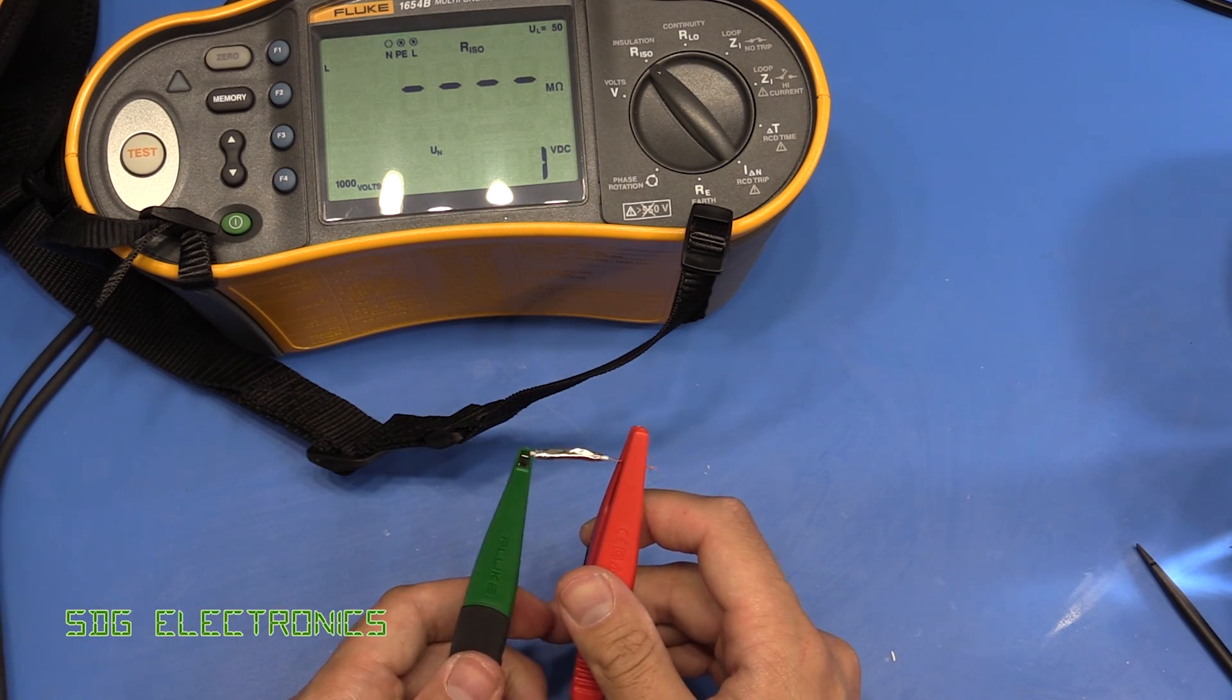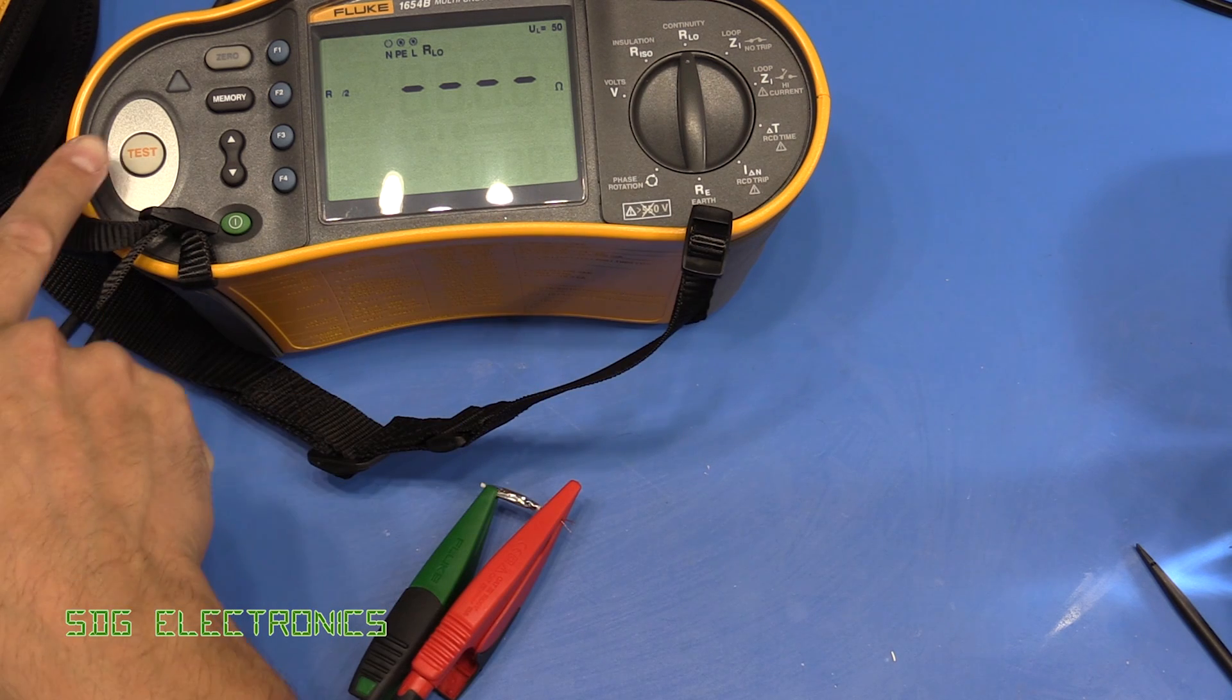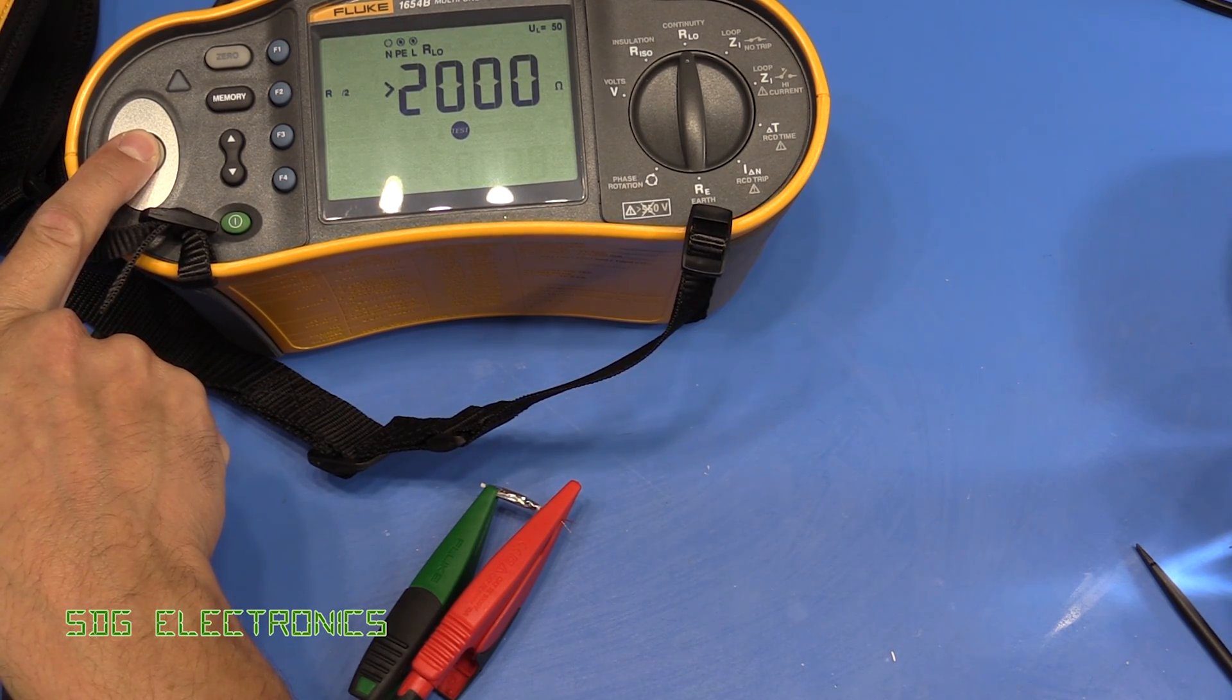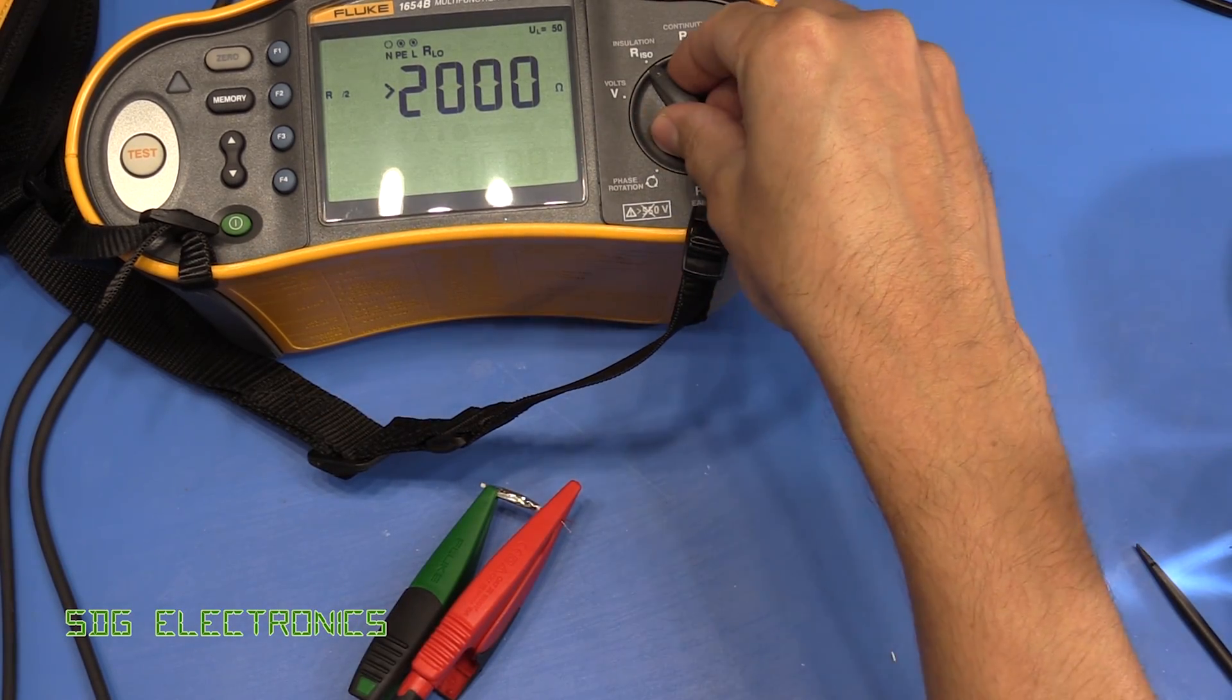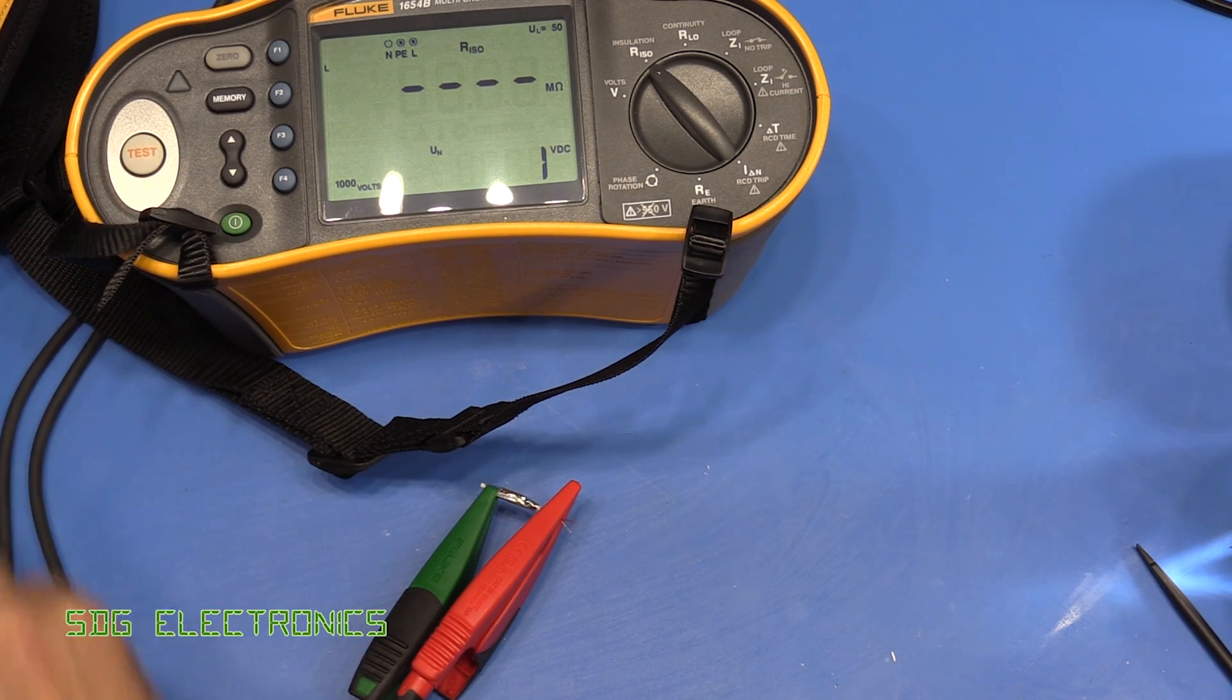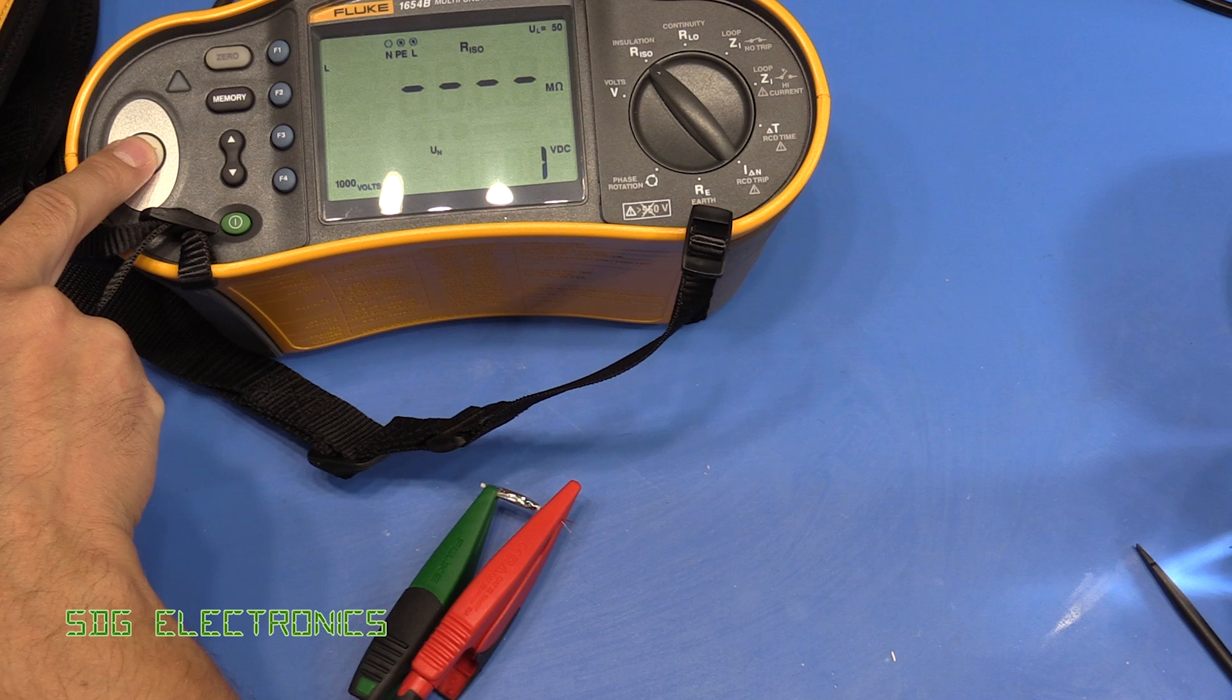Just testing it on continuity, if we press the test button we can read that the impedance is greater than 2,000 ohms. That's using a low voltage method. Then we can do the insulation test. We've got 1,000 volts selected which is our typical maximum that we'd ever want to test at. Let's see what we get.